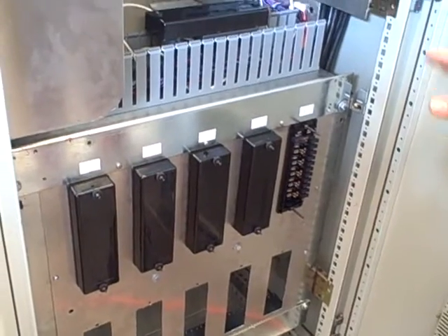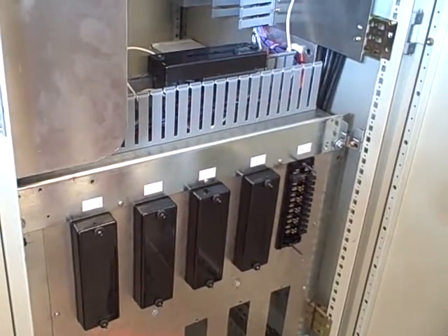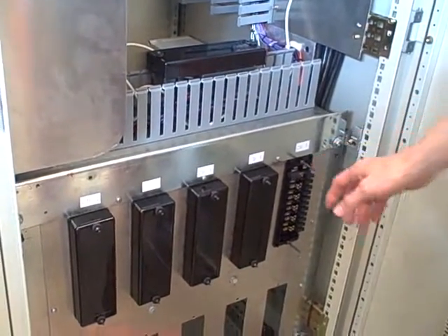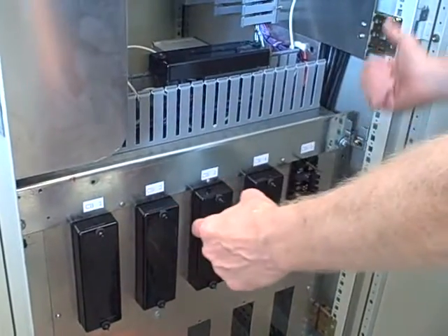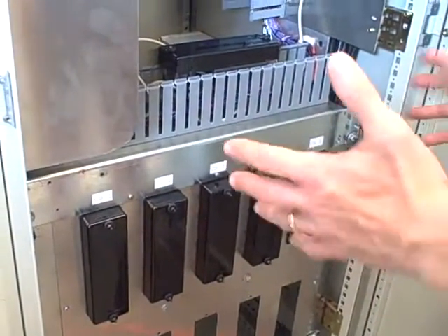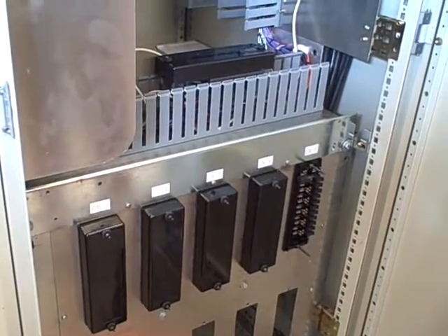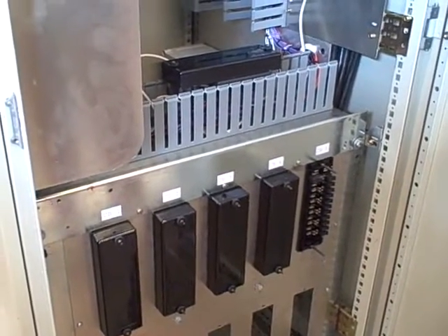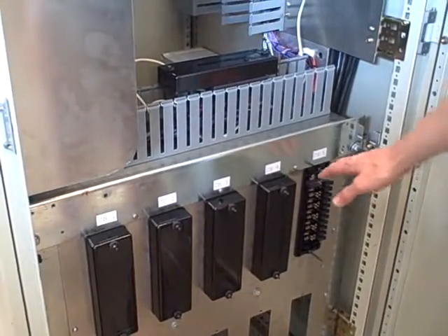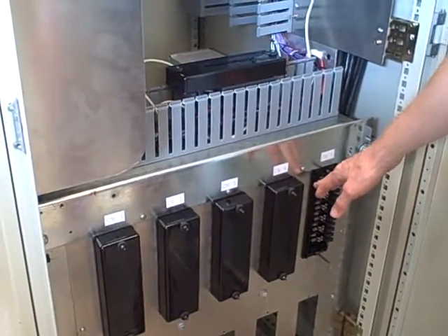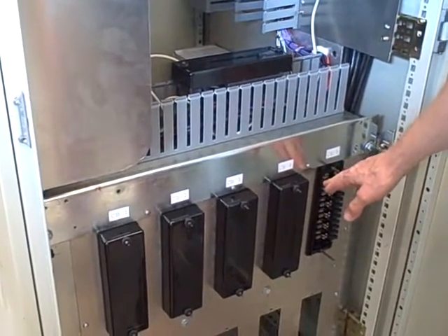Still, this caused the substation to trip offline, because in that moment, it did not see an equality between current in and current out on A phase, and it thought we had a bus problem. So it's an illustration of how the 87 bus differential protection works, and also, like I said, a cautionary illustration of what not to do on the system unless you know exactly what you are doing.